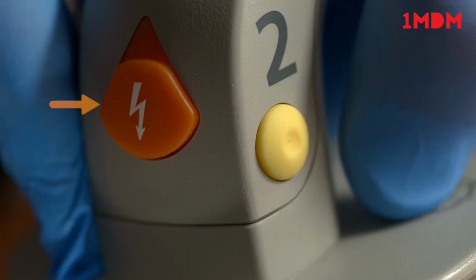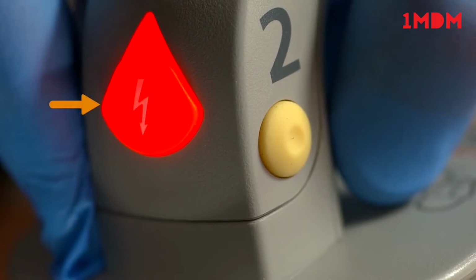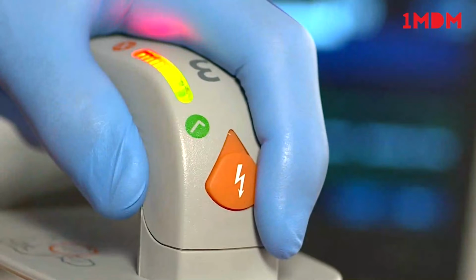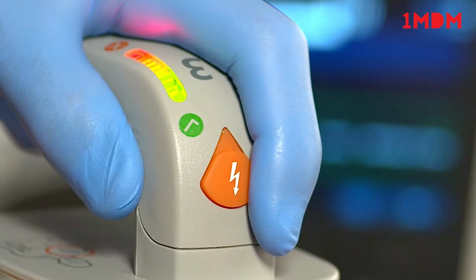Both paddles have orange shock buttons that flash when the defibrillator is charged, and the sternum paddle has a patient contact indicator with these icons to assist in achieving good patient contact. Orange or red lights indicate poor patient contact, while green indicates good contact is made.